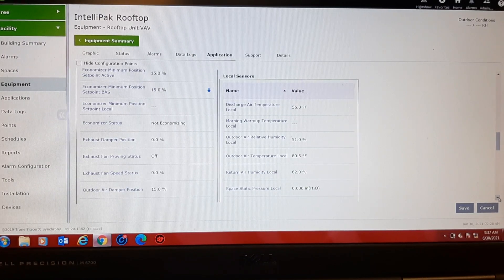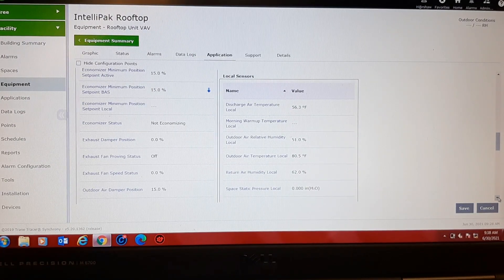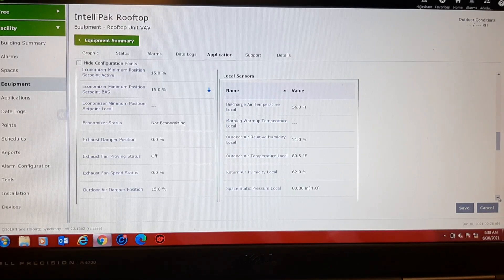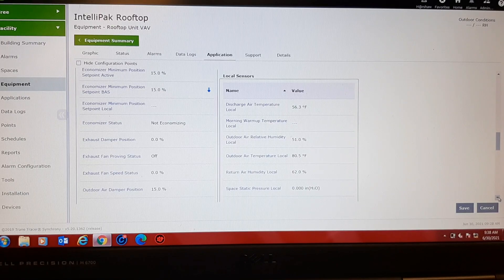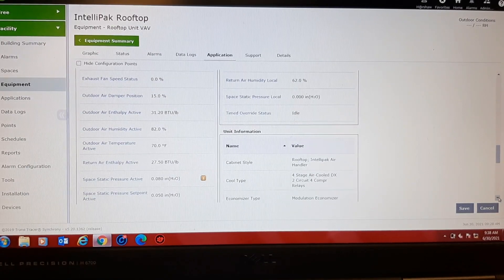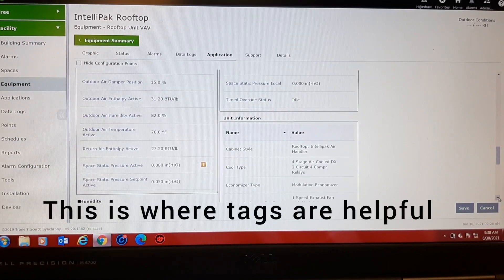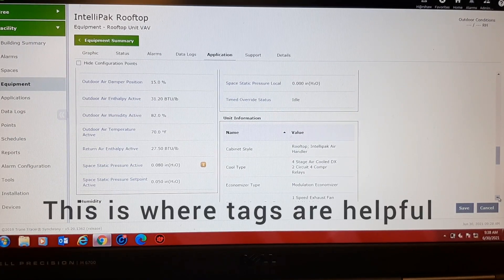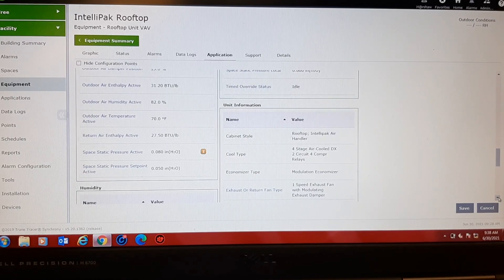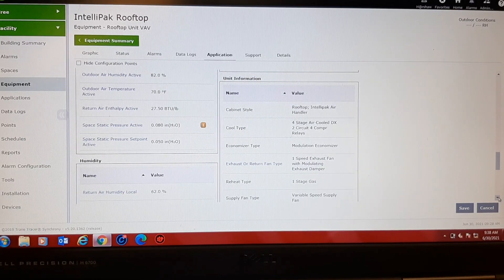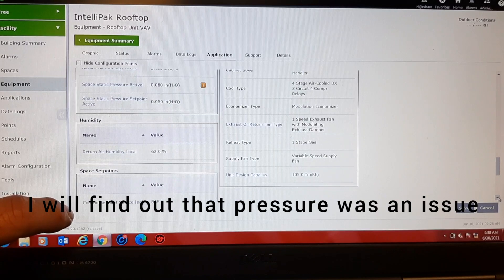Now the next question I'm going to ask is, because there was a tag when we did the PM, I believe last week, the 23rd or so, that when they restarted, the economizer was at min position, but the exhaust fan started running and drew a negative in the building. He didn't have an answer for that. And after reset, everything went to normal. And it seemed normal when I got here today, unless it's doing something weird.